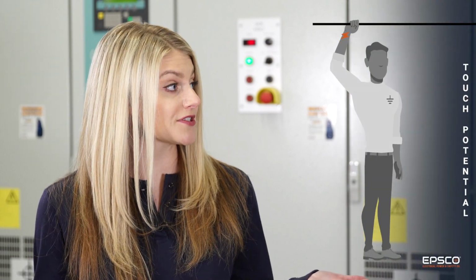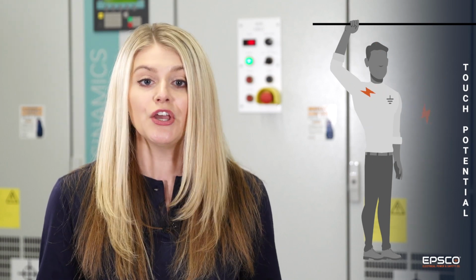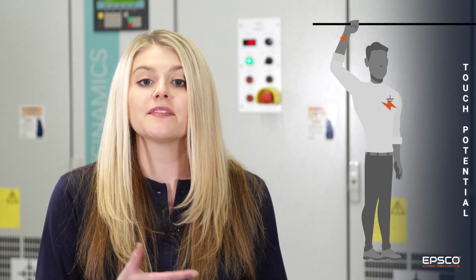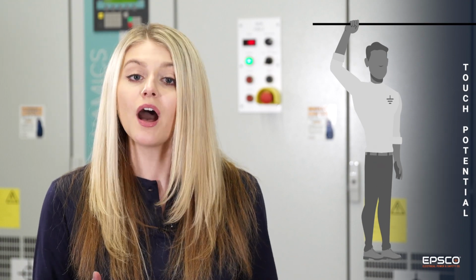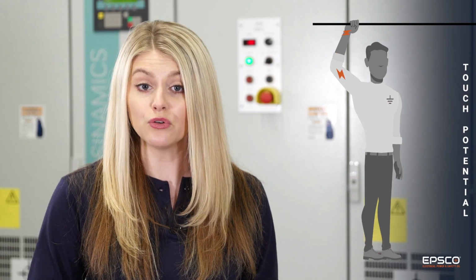If you find yourself in a situation where you need to exit an area with step potential danger, put your feet together and hop to safety. Touch potential covers every pathway that's not foot to foot. So it's a lot more common, especially inside industrial facilities. Many times, current enters through one hand and will exit another part of the body that's in contact with a grounded frame or other energized conductor. This could be your other hand, shoulder, head, chest, or legs.